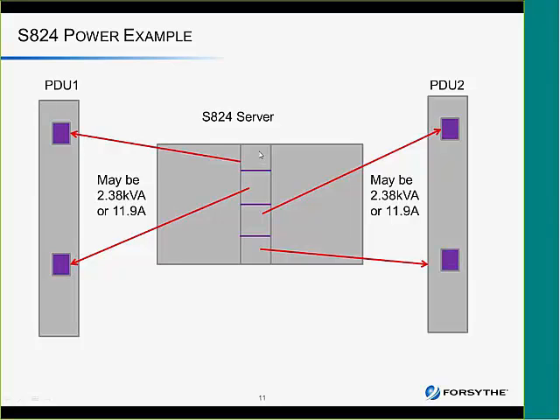So here's my two power supplies that we'll call the live ones. They're going over to PDU 1, and they're going to pull somewhere around 11.9 amps or 2.38 kVA. And then here's my redundant pair to another PDU, and they're going to pull the same amount. Obviously, only two of these are working at a time, but like I said, we don't know which two. But it just gives you an idea. And all the other servers except the E870 are going to be one power plug going each way. It's just because of the amount of kVA and amps this pulls. Clearly, since I have a 10 amp limit on each plug, I can't put just one plug over there. It has to be two. So hopefully this is making sense.